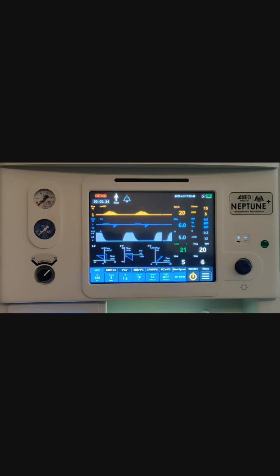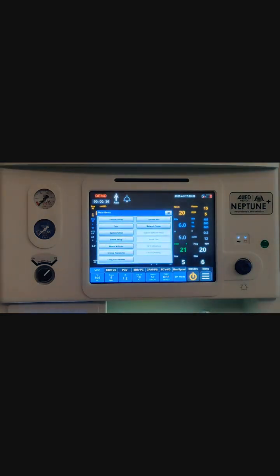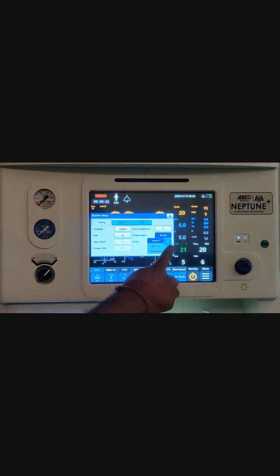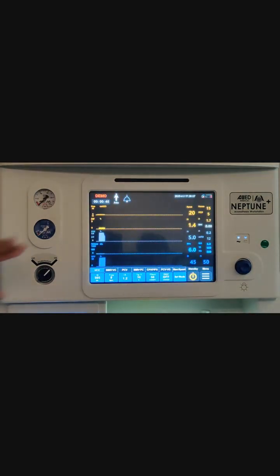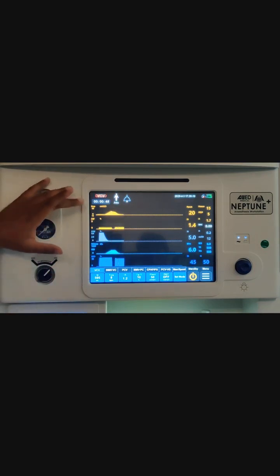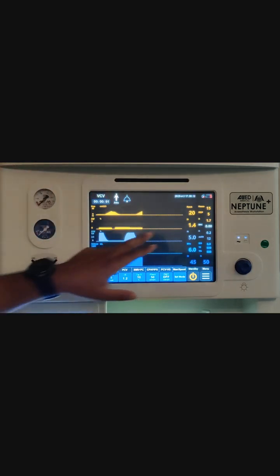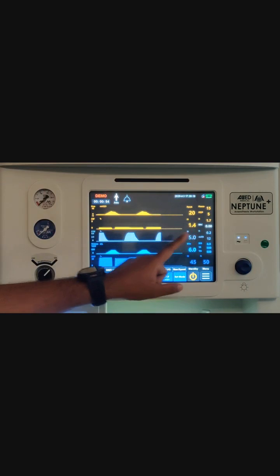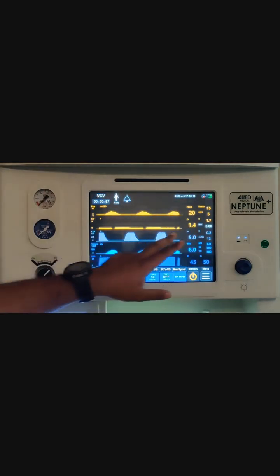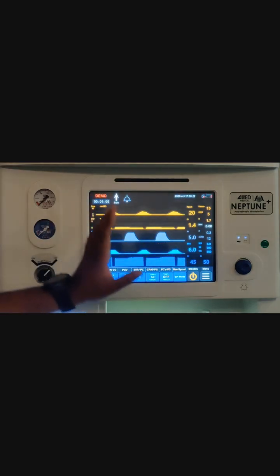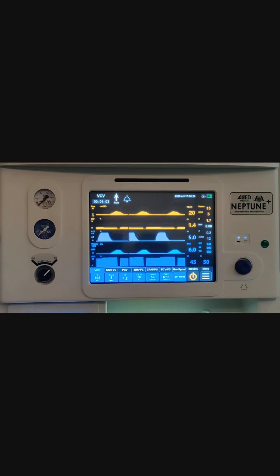A very important feature that we have upgraded in the machine is that this machine will now be coming with the optional upgradability to AGM, that is the anesthetic gas module, as well as the ETCO2. So you can upgrade the machine with the anesthetic gas module and you will be getting the waveform as well as the monitoring on the screen itself. So for that we have AG wave. So on this screen, on this layout, you will be getting whatever anesthetic agent is being delivered to the patient, the FI value, the ET value, along with the MAC value, that is the minimum alveolar concentration, as well as the CO2 value. So you will be getting the ETCO2 and FiCO2 also. So this machine comes with this feature that it can be upgraded with the AGM as well as the ETCO2.